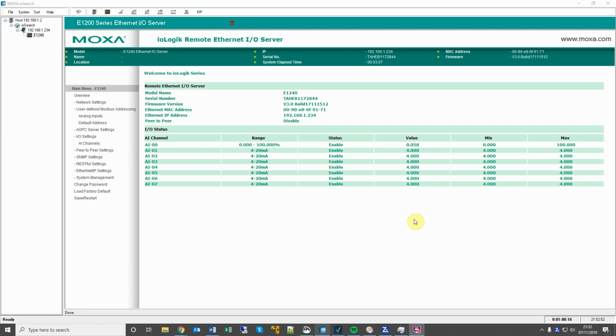This is the first of a series of videos on getting ModBus TCP data into Ignition SCADA. This first video is on the Moxa E1240, which can be either 0 to 10 volt or 4 to 20 milliamp across 8 channels.